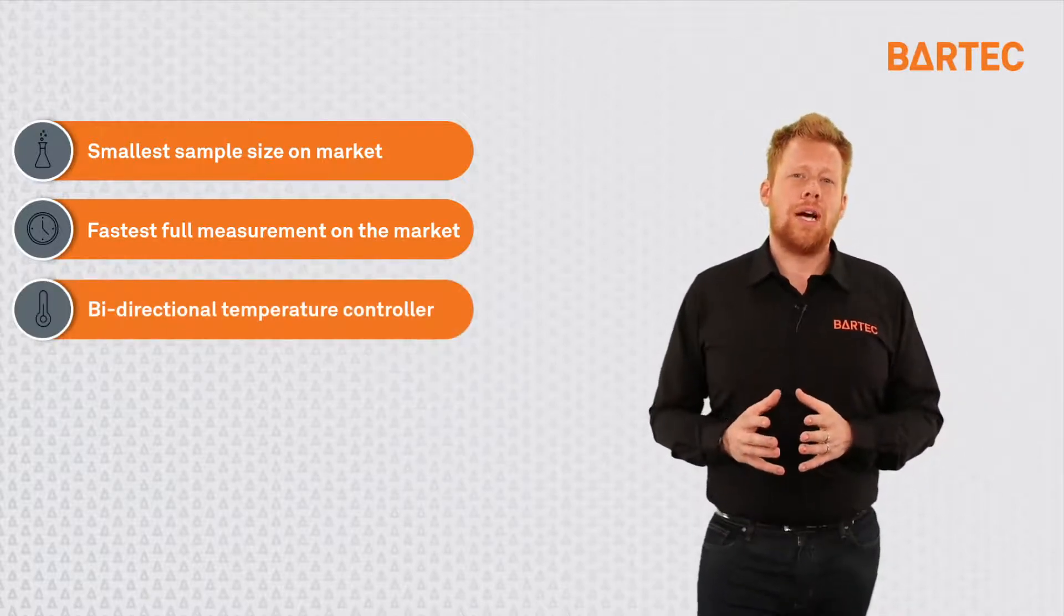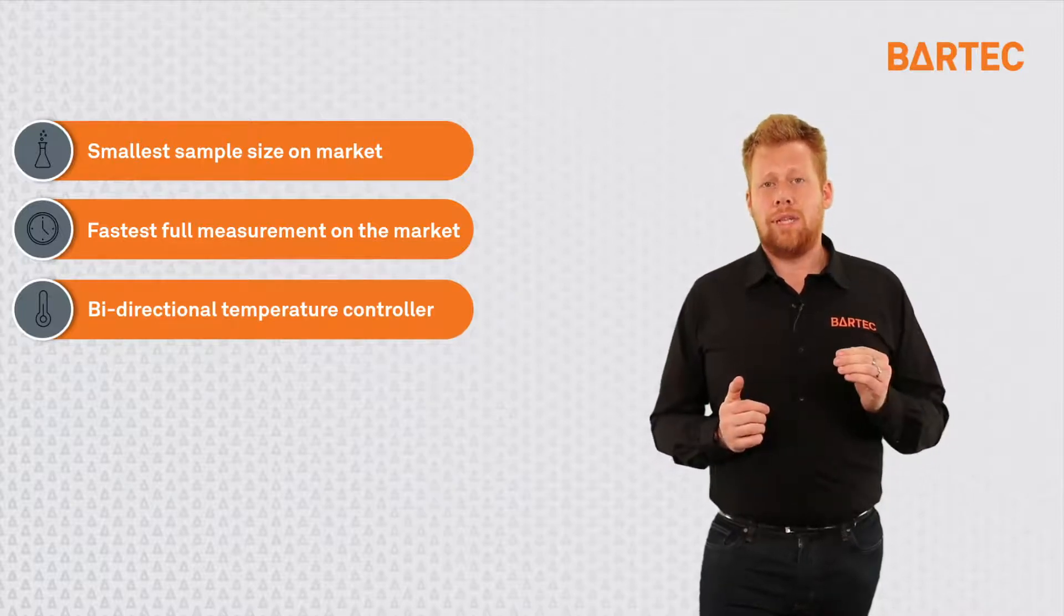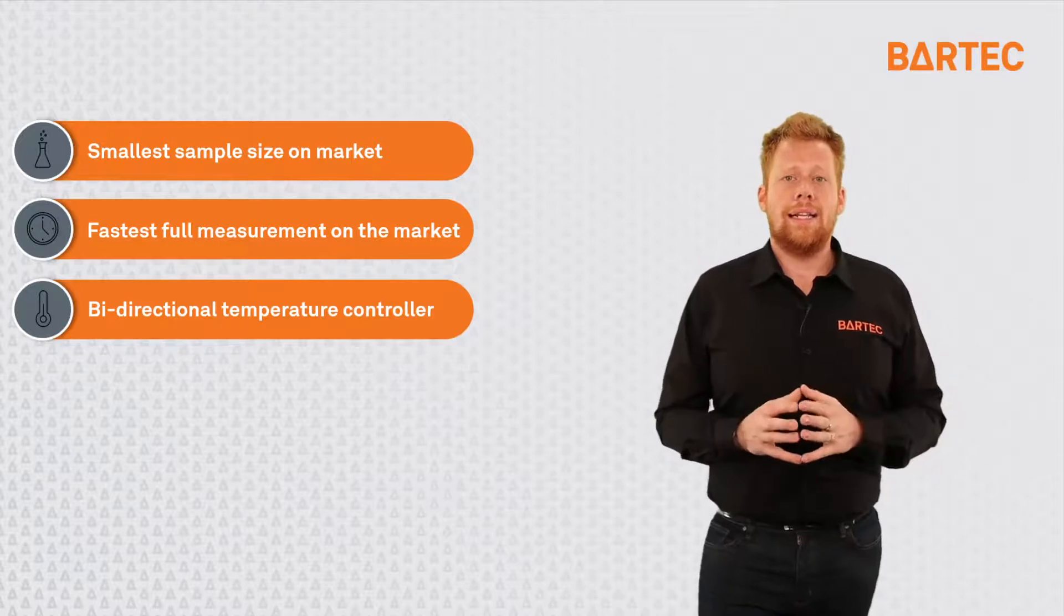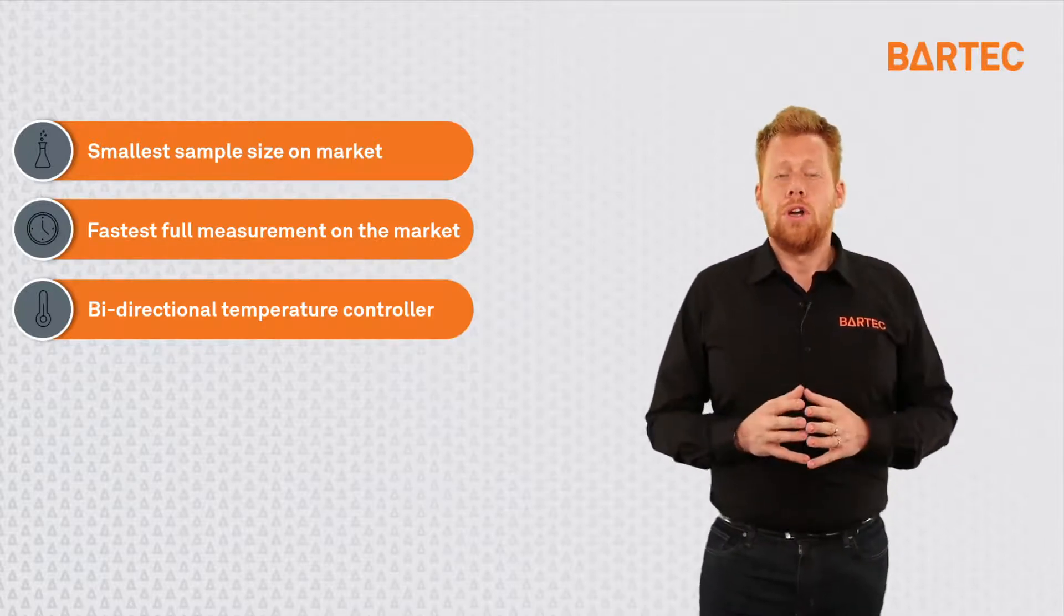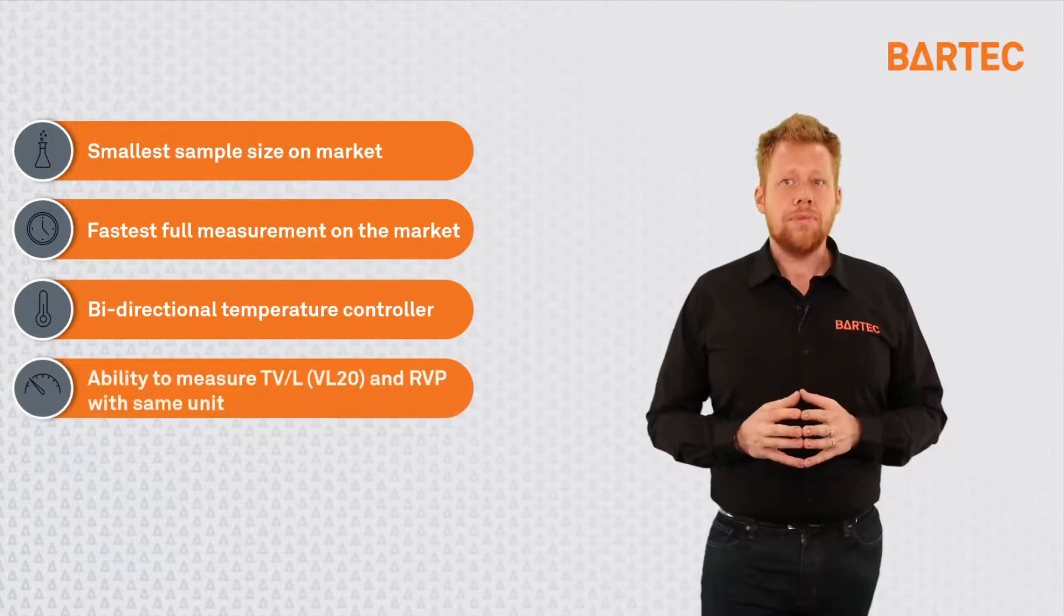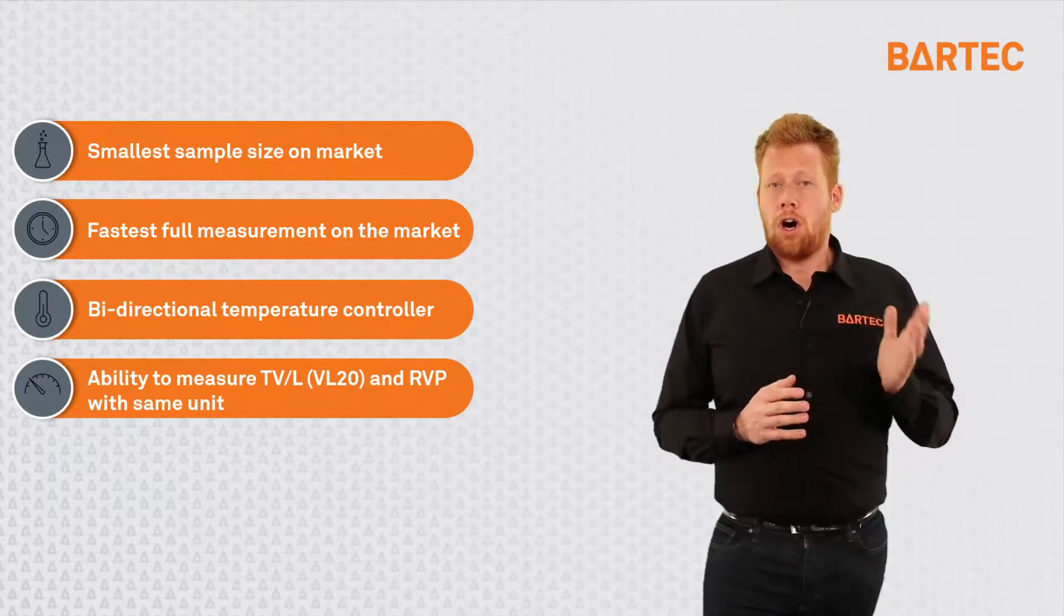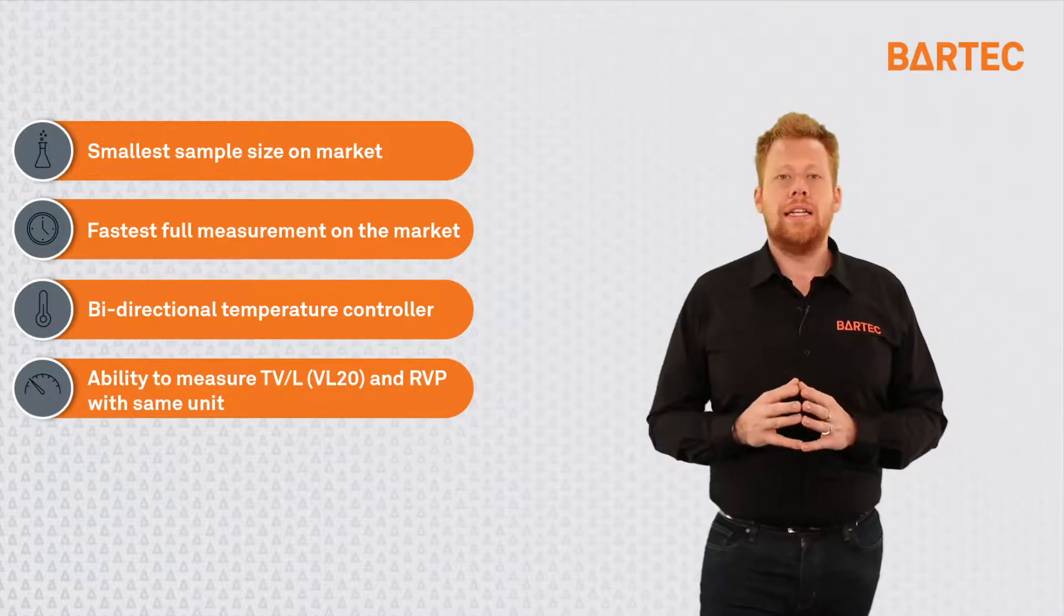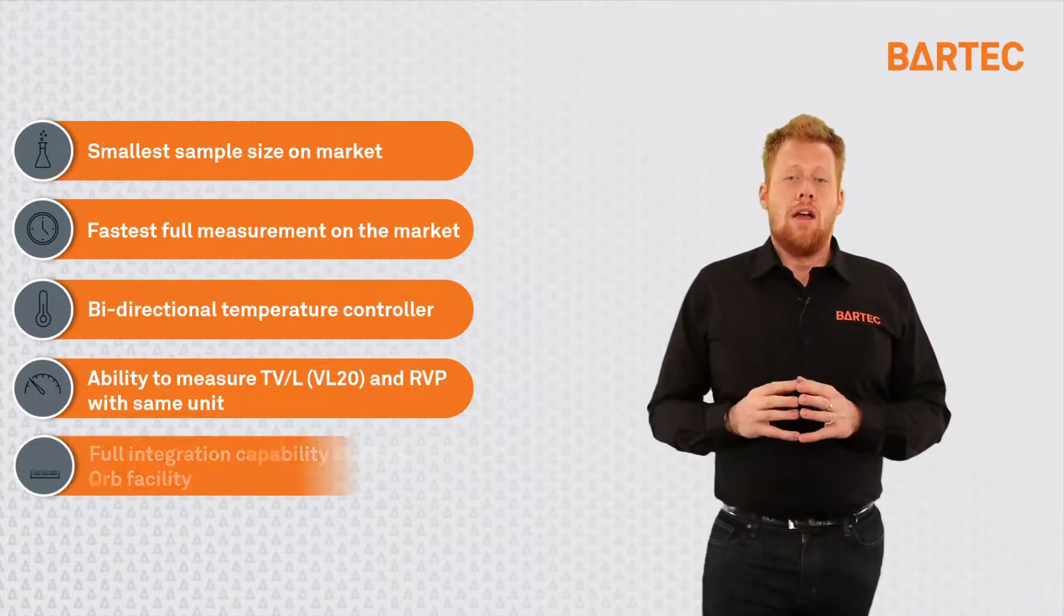The system also has a bi-directional temperature controller. This means that the sample can come hotter or cooler than the RVP and the analyzer will take care of modifying the temperature in order to do the RVP measurement at 100 degrees Fahrenheit. The system also has the ability to do a dual measurement, RVP and TV over L, more specifically VL20, thus combining two analyzers in one.